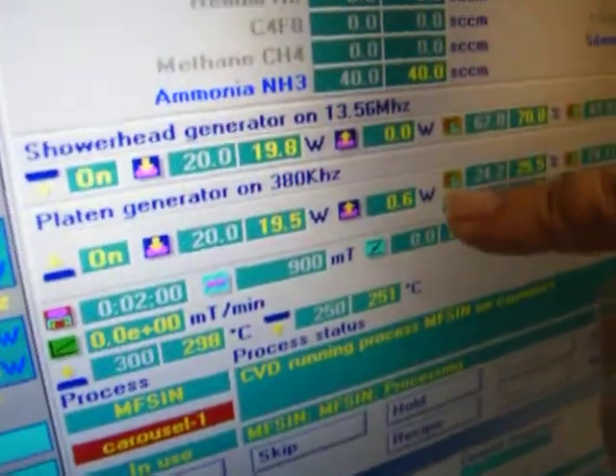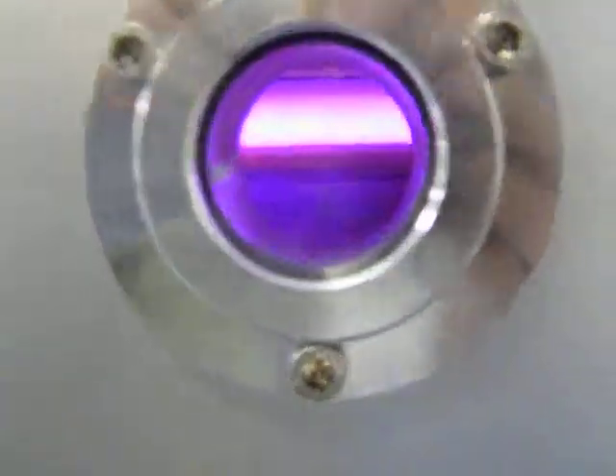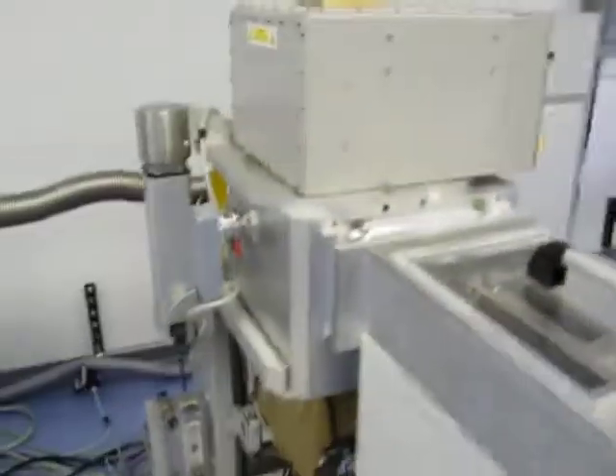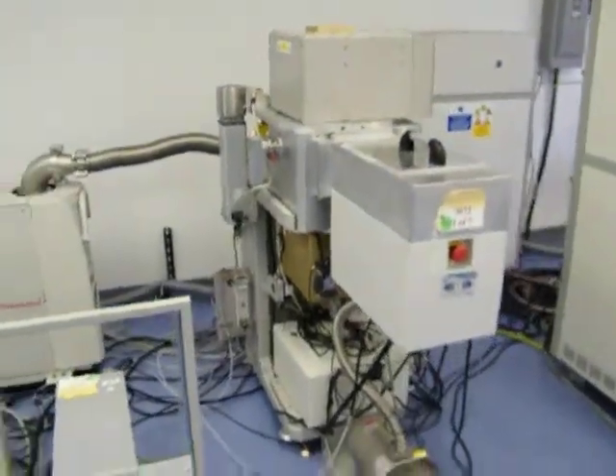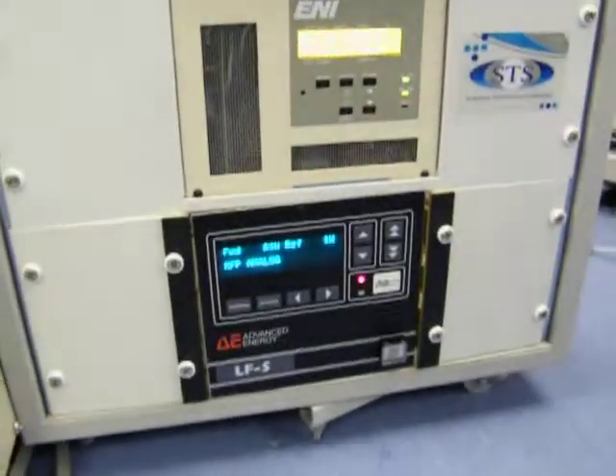Here we show reflective power — so it's tuned very nicely. If you go look in the window you'll see the plasma. The generators are on, normal, no problem. All the generators are on, running smoothly — 20 watts output each.